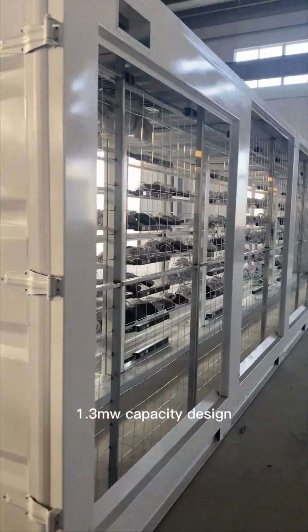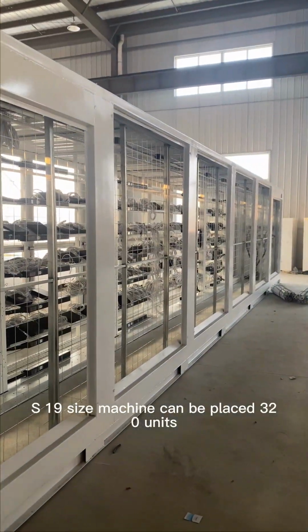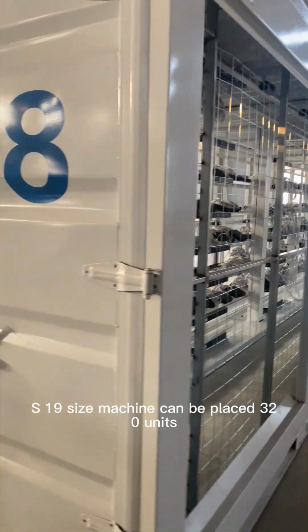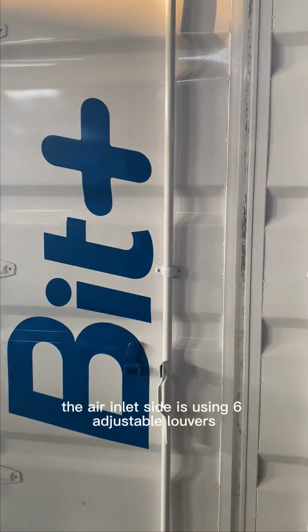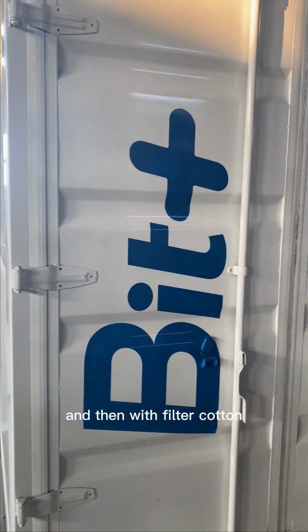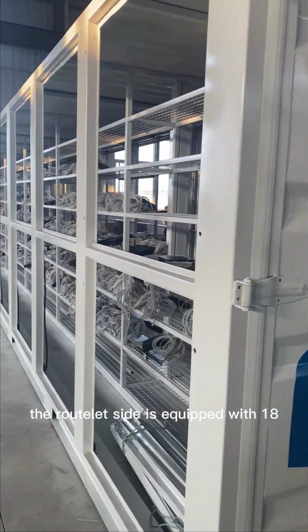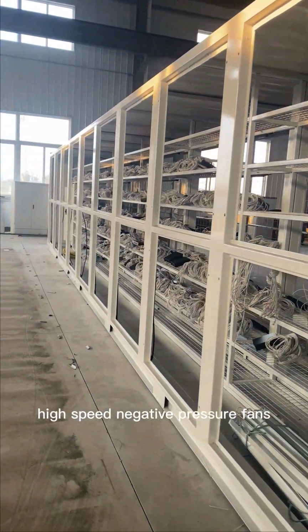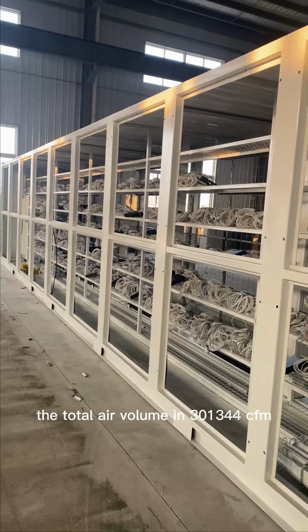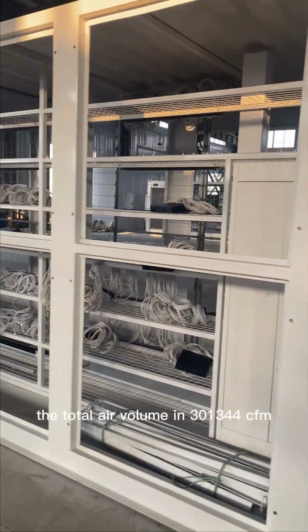It has a 1.3 megawatt capacity design, and an S19 size machine can have 320 units placed. The air inlet side uses 6 adjustable louvers with filter cotton, and the outlet side is equipped with 18 high-speed negative pressure fans. The total air volume is 301,344 CFM.